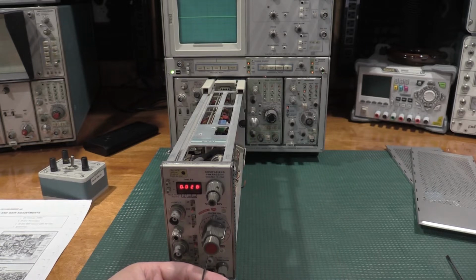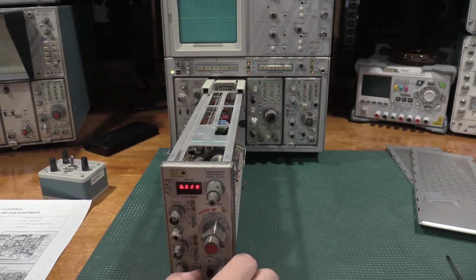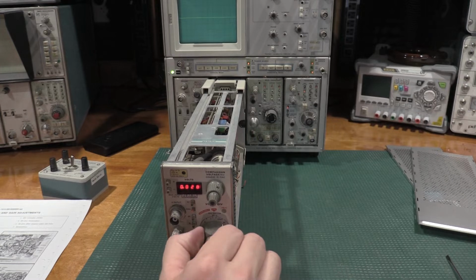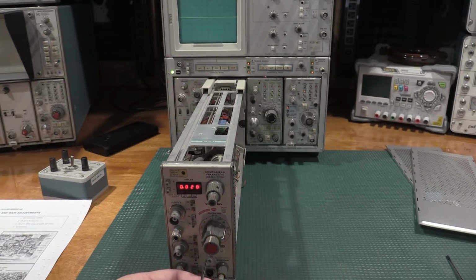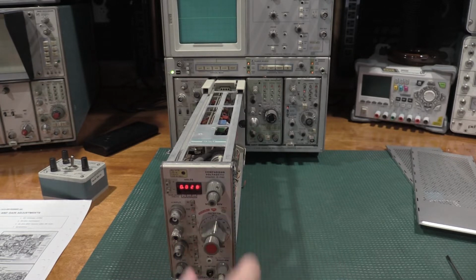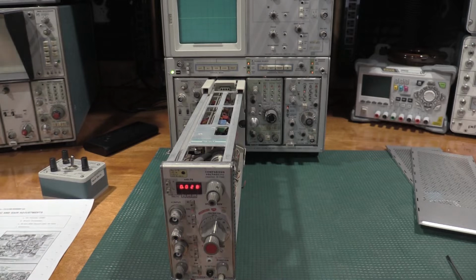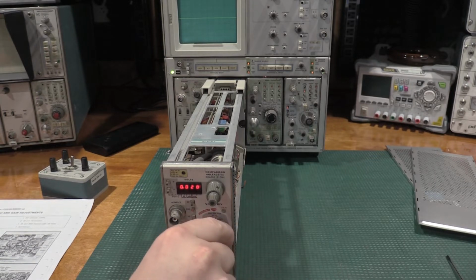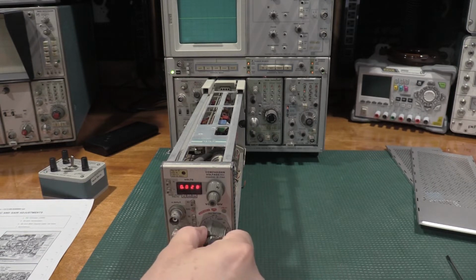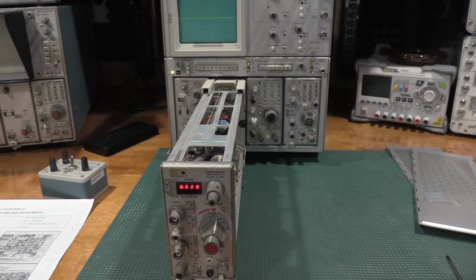So it's adjust position at 50 and align at 10. And there we go. So you adjust the positioning control with it at 50 millivolts, and then you align the step balance at 10 millivolts. And that lines up real good.